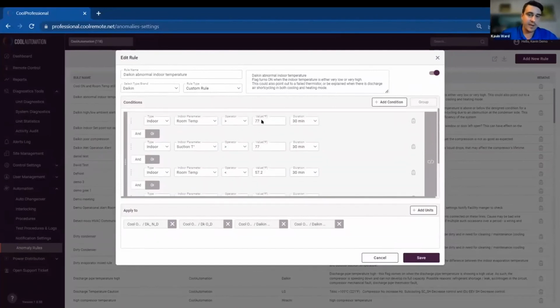If it's too hot, it could indicate that a window or a door is open. If it's supposed to be in cooling and the system's not able to satisfy a 74-degree set point and it's 78 degrees in the room, that could indicate very readily that something is wrong with the system, whether we're not receiving the performance that we should. It could be low on refrigerant. There could be poor airflow across that indoor unit, so not enough heat transfer. But even a rule as simple as this can go a long way with enhancing energy optimization for your building. And I hope that covers at least the anomaly rules.